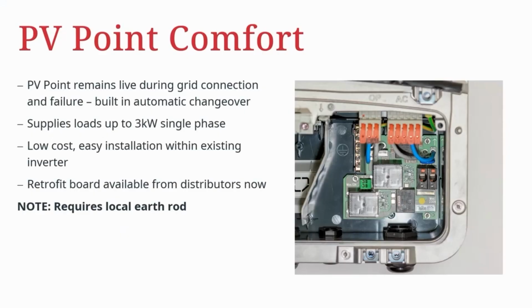Please note, for all of these solutions you do need to have a local earth rod on site. This is to provide your protective earth in case there is a disconnection from the grid earth outside the property. For added simplicity and ease of operation, Fronius now have the PV Point Comfort solution. This is a retrofittable circuit board which fits into the AC compartment of the Gen24.